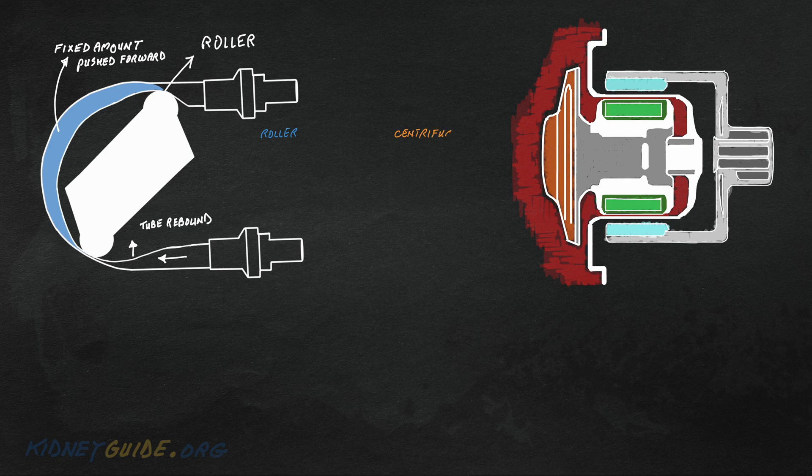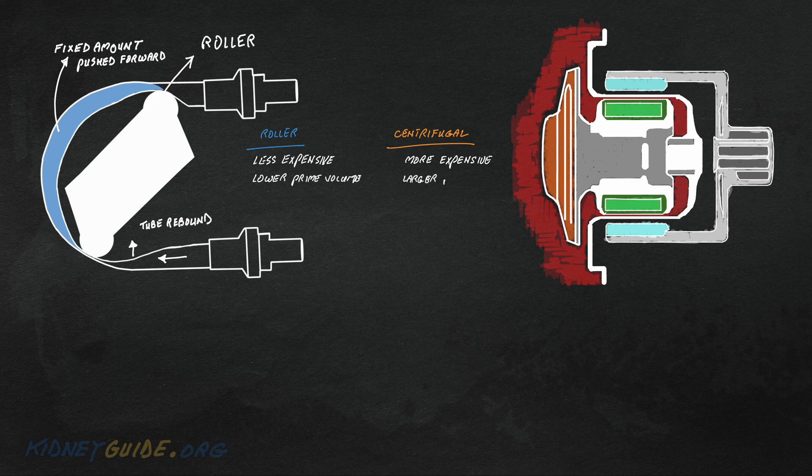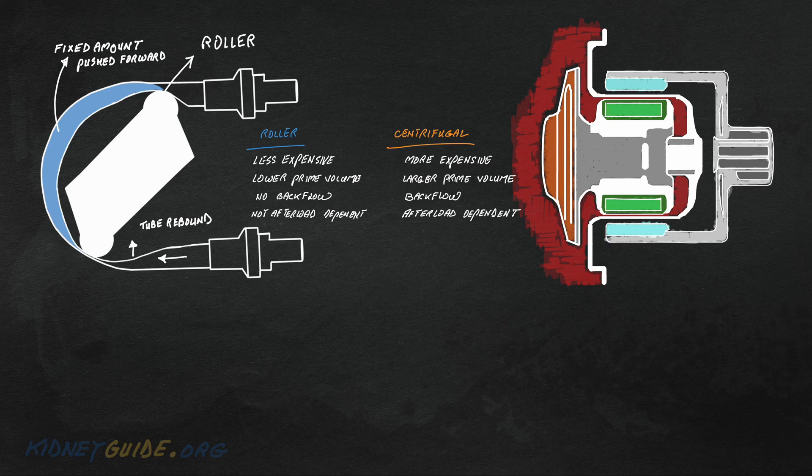When we compare roller to centrifugal pumps, they are cheaper and need less blood for priming. They are also constant volume pumps, which means they maintain constant speed and flow regardless of afterload pressure.